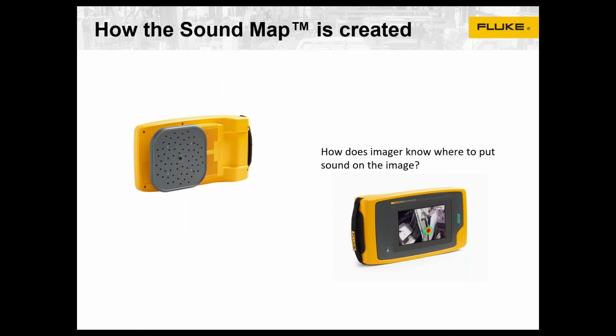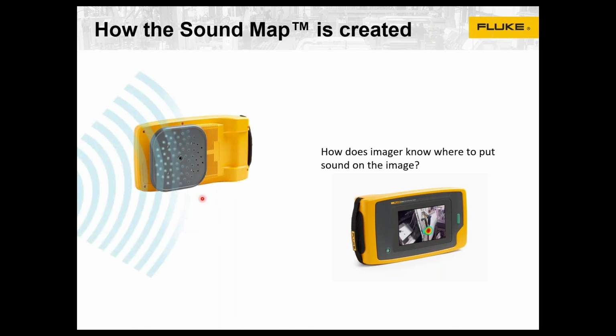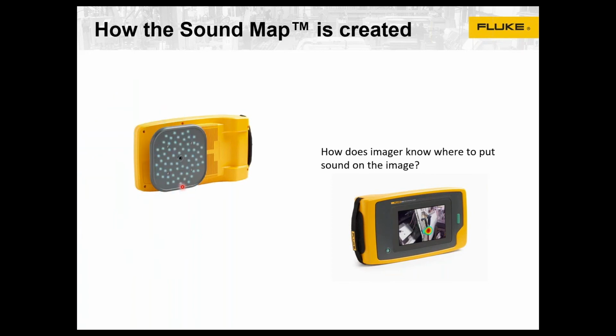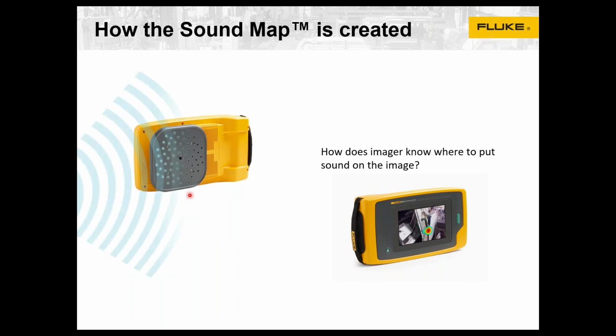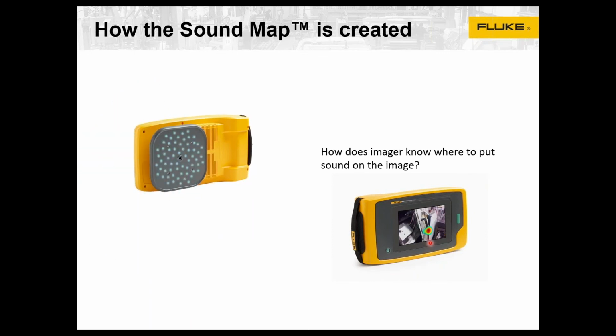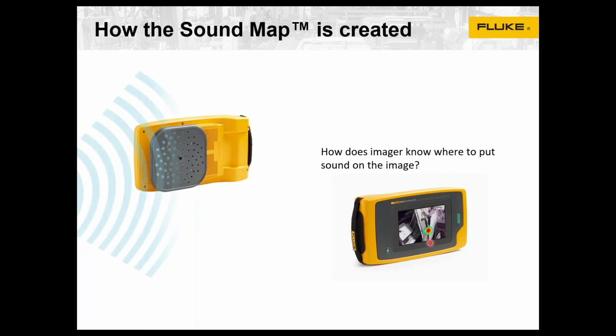So how are we doing that? As I mentioned, it's ultrasonic. This is the tool. We're seeing both the camera display side, the operator side, and the measurement side. This is a bank or an array of sensors that pick up ultrasonic, specially arranged. And as sound is emitted, it strikes the microphones, and through processing and measuring slight time differences in when the sound arrives at each of the individual microphones, it's able to not just detect, detection's important, but to locate that leak. Where is it? It's able to place that sound map on the screen. That's where the time savings comes in. You don't have to interpret it. It's very definitive.